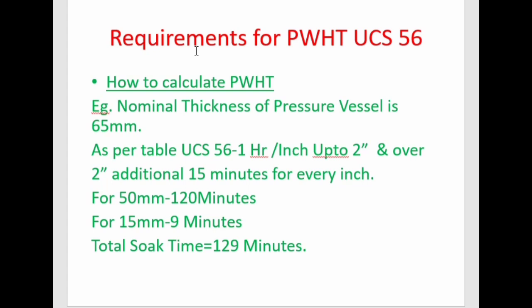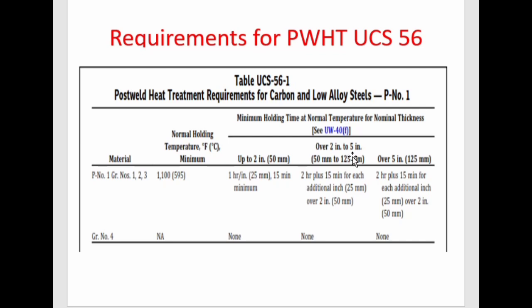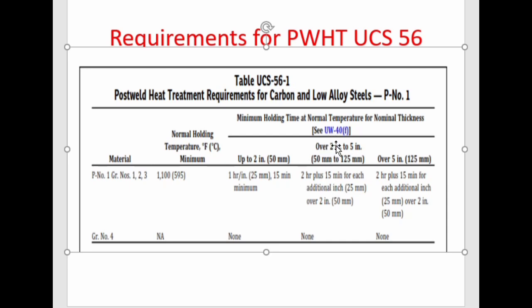Now let's calculate the soaking time period — not soaking temperature, but soaking time period. Consider a nominal thickness of 65 mm. As per Table UCS-56, 65 mm is greater than 2 inches (50 mm), so it falls under the category of over 2 inches to 5 inches, which requires 2 hours plus 15 minutes for each additional inch.